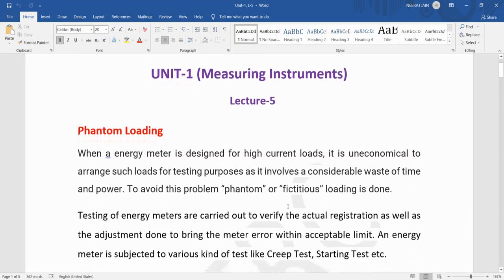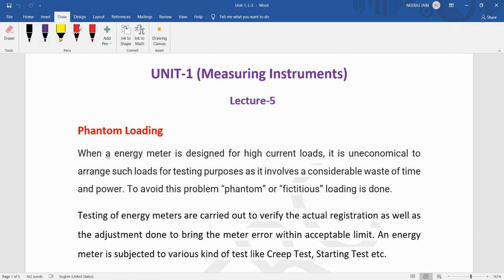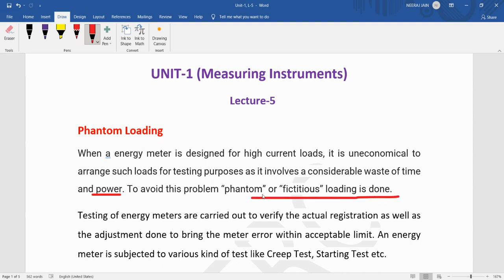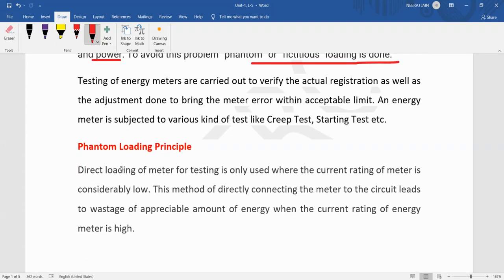Okay dear students, welcome to all of you. Today we are going to discuss about the phantom loading. When an energy meter is designed for high current loads, it is uneconomical to arrange such loads for testing purpose as it involves a considerable waste of time and power. To avoid this problem, phantom or fictitious loading is done. We will see what is the basic principle of phantom loading.